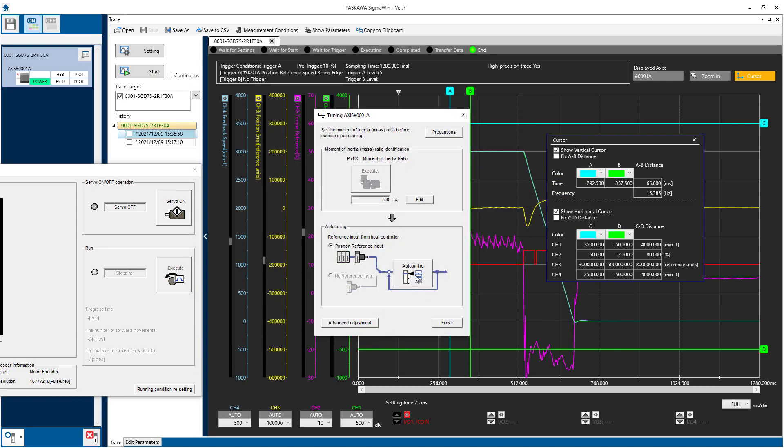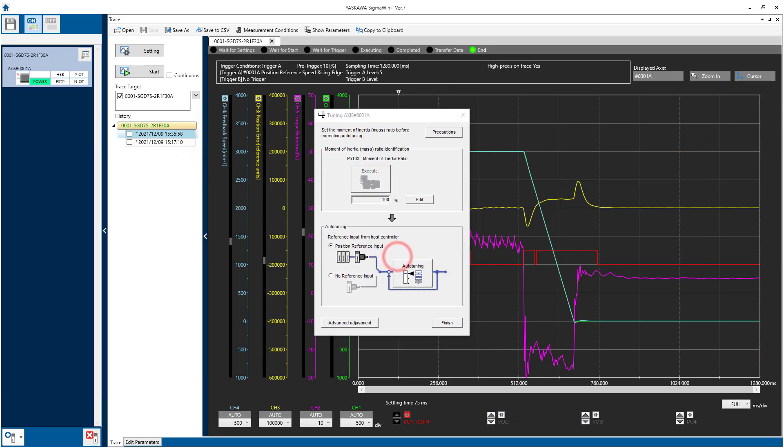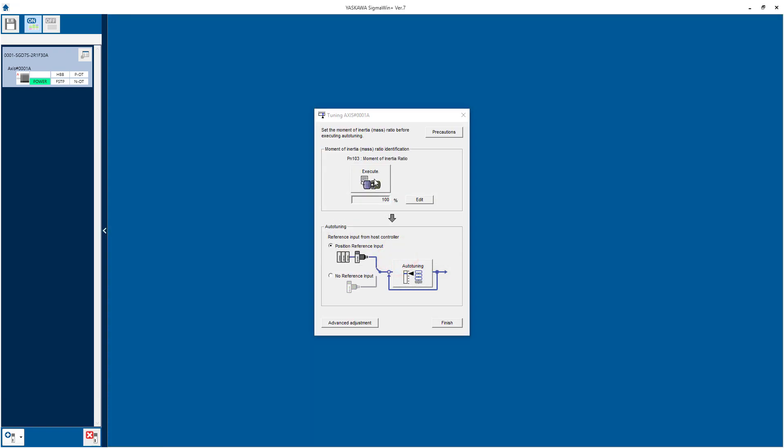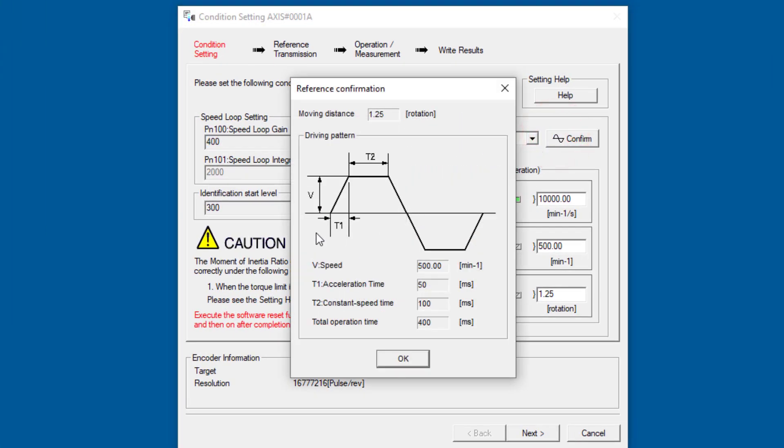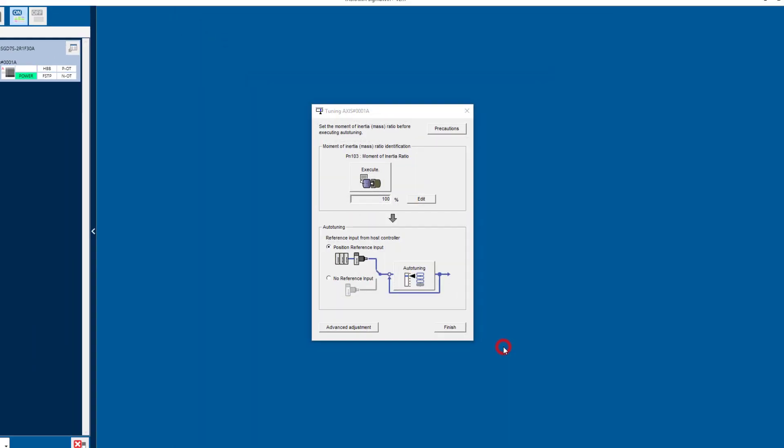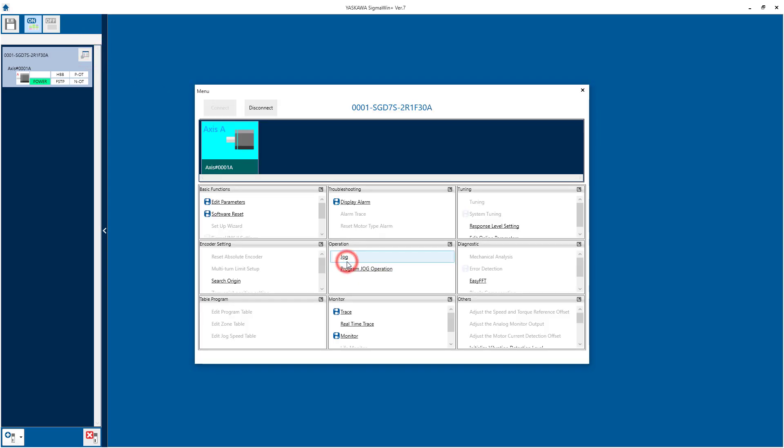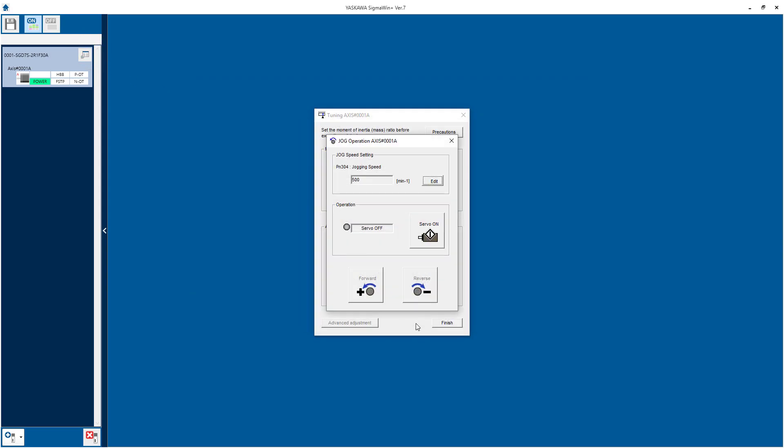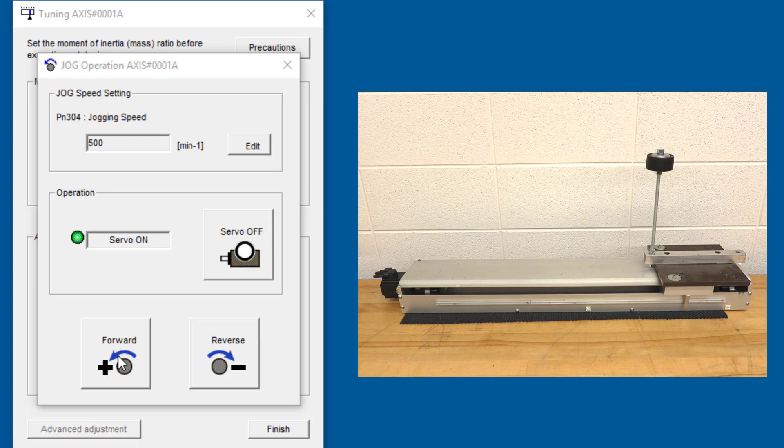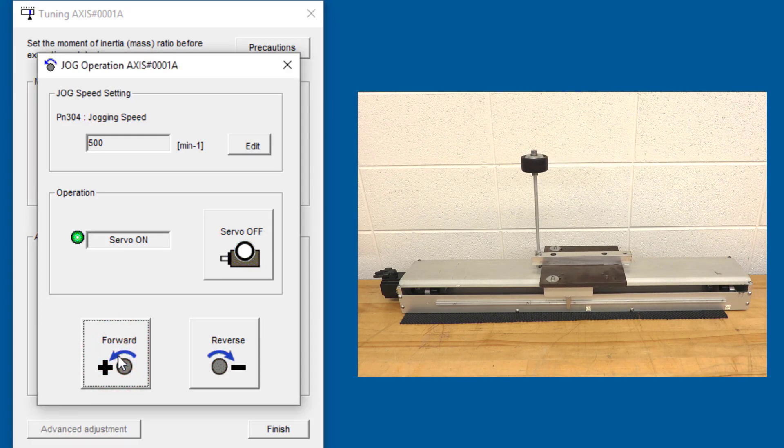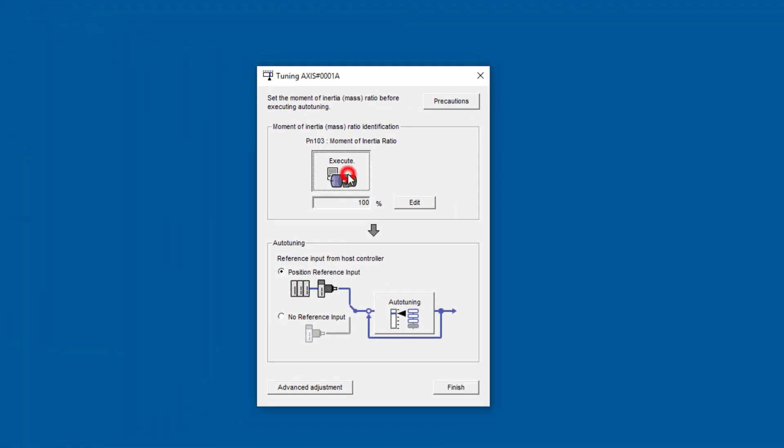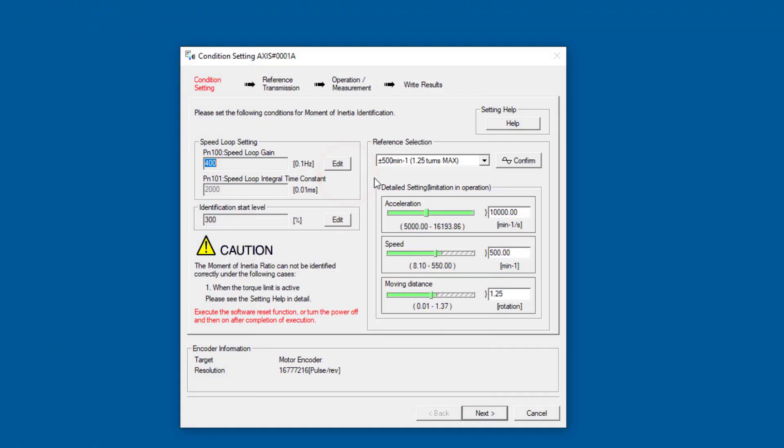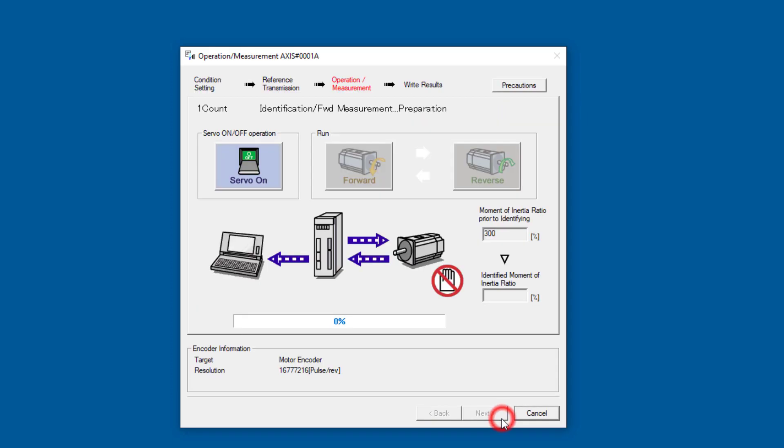Now I can go back into Tuning to execute. But before you do Auto-Tuning, you should find the inertia if you don't know it, so I will go through that. It's grayed out, so that means I need to close all the other windows that are conflicting with this. Now I can execute. And you see in the confirm button that this will do both a forward and reverse move. So I better cancel this and jog the motor back to the middle of the actuator here. I'll jog forward to about the middle.